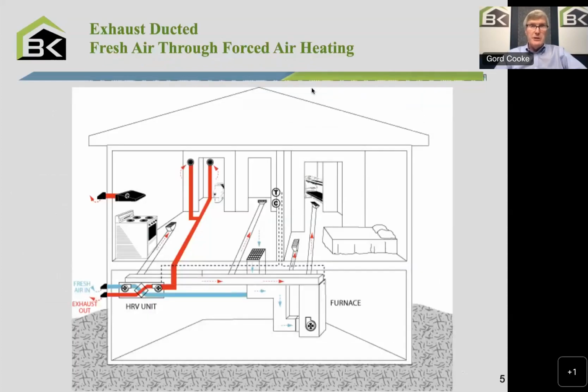And the most common installations of these, typically you'll see the HRV unit at the bottom. You'll see the fresh air coming in, and typically in houses that have forced air heating systems, furnaces, for example, often the fresh air, the blue line, will be brought in through the HRV and delivered into the return air system of the furnace to allow it to be distributed throughout the house. These are called exhaust ducted systems or partially ducted systems.